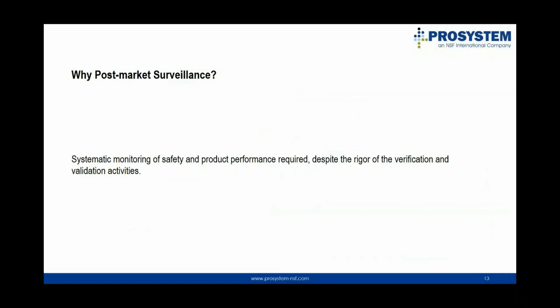Secondly, no matter how accurately you perform verification and validation tests at the design stage, there is no way to accurately simulate every possible real-life situation. That is why systematic monitoring of the product performance in real-life situations after market introduction is necessary in order to ensure that the identified device risks, risk control measures, and residual risks remain acceptable, but also to ensure the ongoing validity of the benefit risk determination, the state of the art, and other considerations.